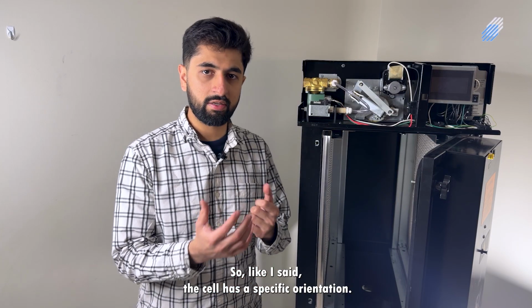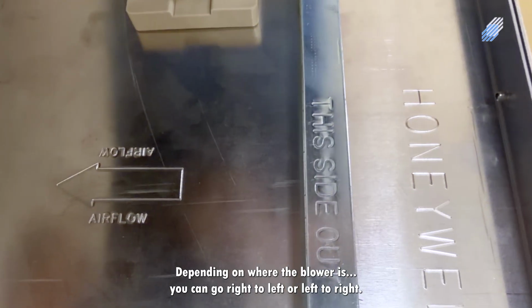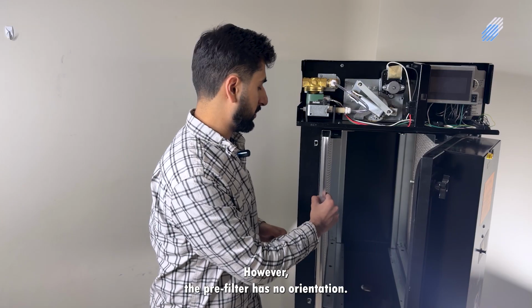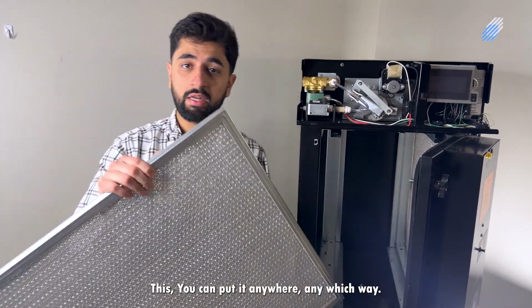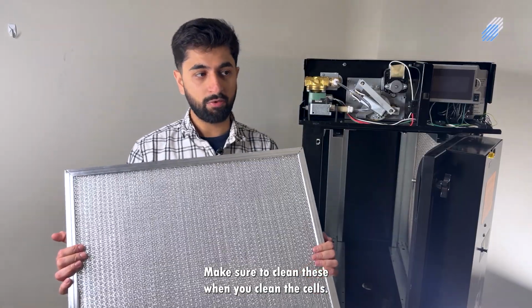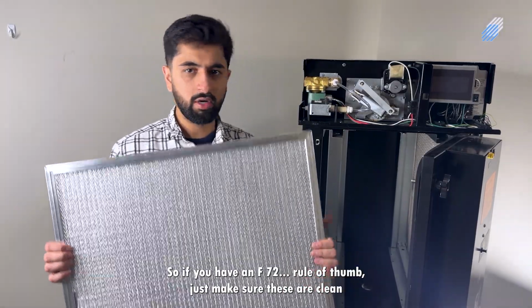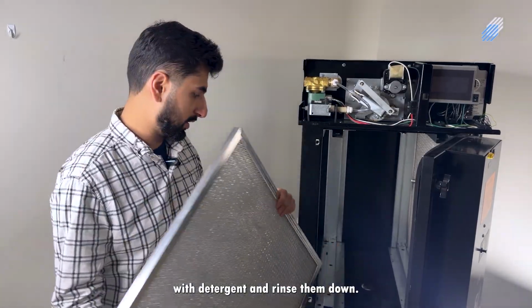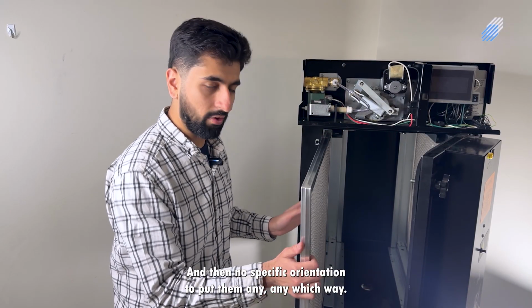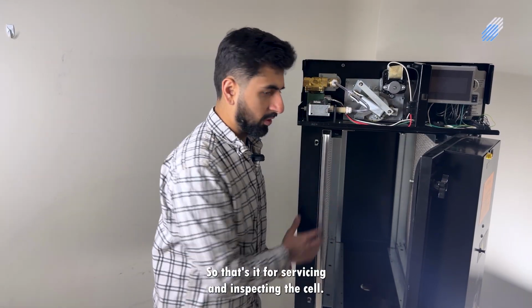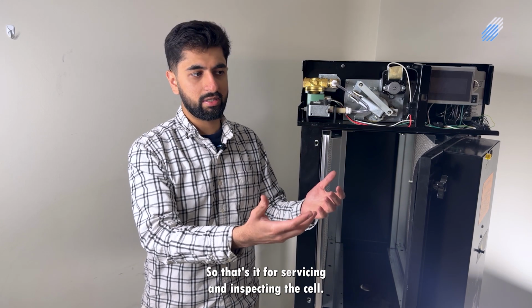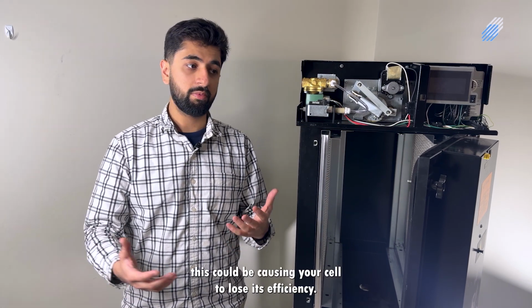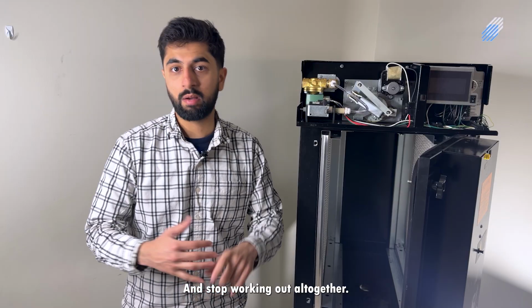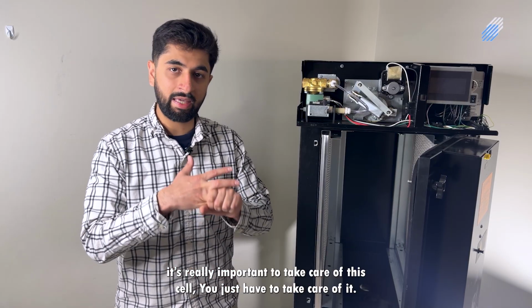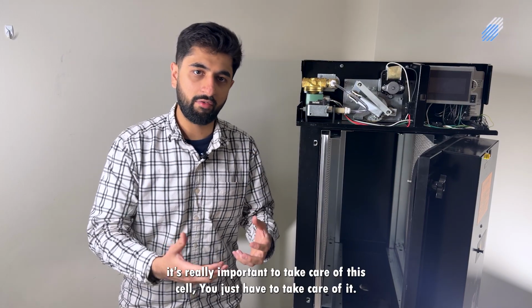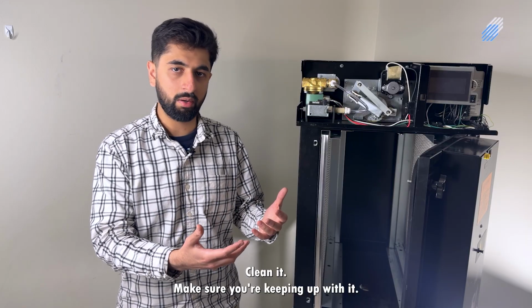Like I said, this cell has a specific orientation depending on where the blower is. You can go right to left or left to right. However, the pre-filter has no orientation. This you can put any which way. Make sure to clean these when you clean the cells. So if you have an F72, rule of thumb, just make sure these are cleaned with detergent and rinsed down. And then no specific orientation, you put them any which way. So that's kind of it for servicing and inspecting the cell. If you have any of these issues, this could be causing your cell to lose its efficiency and stop working altogether. It's really important to take care of the cell. You just have to take care of it, clean it, make sure you're keeping up with it.